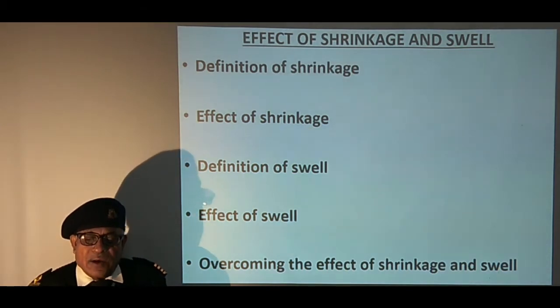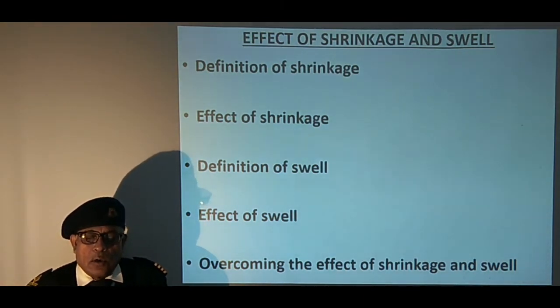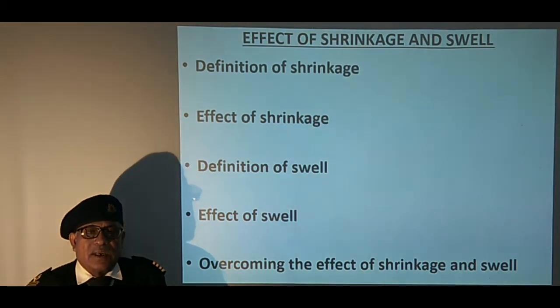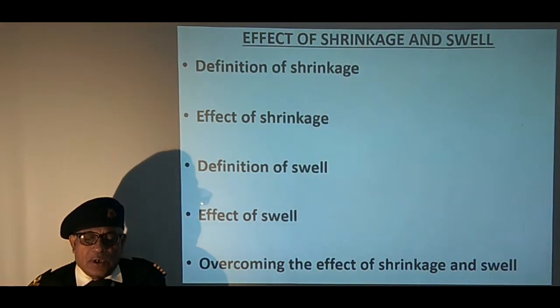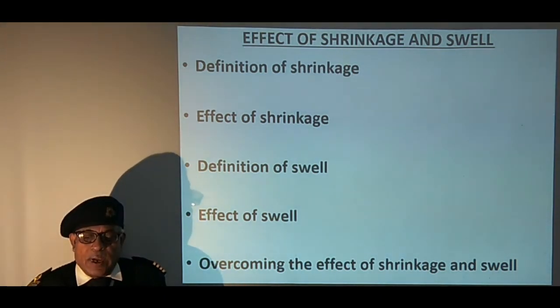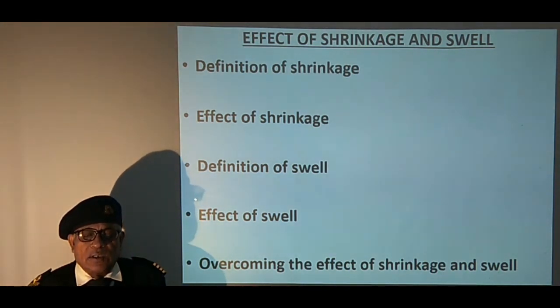The effect of swell and shrinkage can be easily seen by carefully monitoring the boiler water level through the gauge glass when the boiler safety valve is being floated. To overcome the effect of shrinkage and swell, a second element is monitored, which is the steam flow signal. It is more appropriate for the control of water level in the boiler, as the amount of steam outflow should be equal to the amount of water inflow to maintain a steady water level in the boiler.